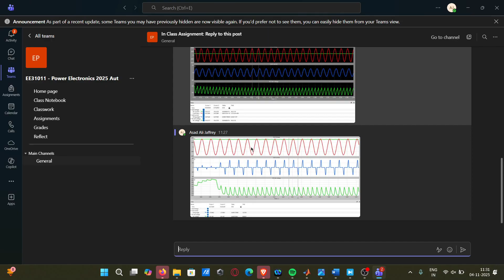Here I am doing current control, right? And I have to maintain the DC link voltage at 400 volt to generate the current, right? If it drops beyond that, probably it won't work. But 400 volt, I have to maintain it, right? So the current that you have to inject from the grid will be decided by this voltage controller, right? So the current reference generation will be decided by the voltage control of this capacitor. Please pay attention. This is an important point.